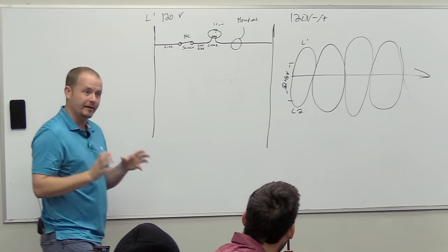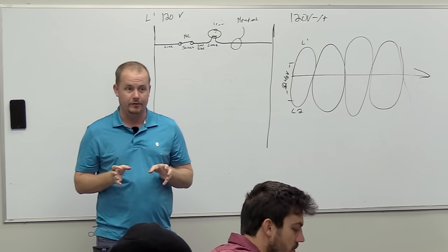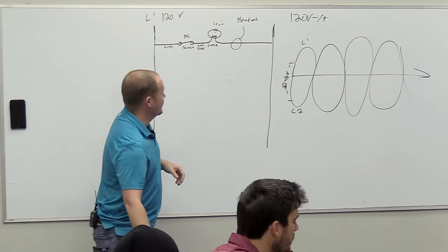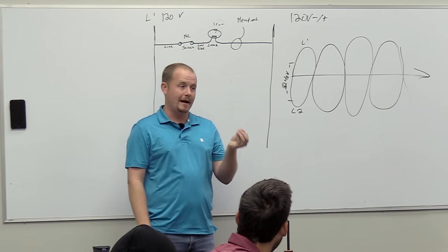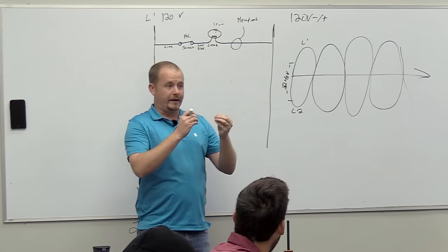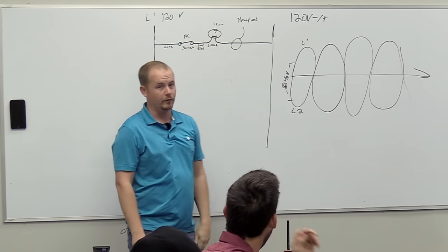So you have to be really careful with the term common. Common means a lot of different things. When you hear it, when you say it, just make sure you know what you're saying, because it doesn't mean ground and it doesn't mean neutral. Alright? When we say neutral, we are talking about a specific thing. We're talking about a circuit that operates on the other side of the load from line on a 120-volt circuit.